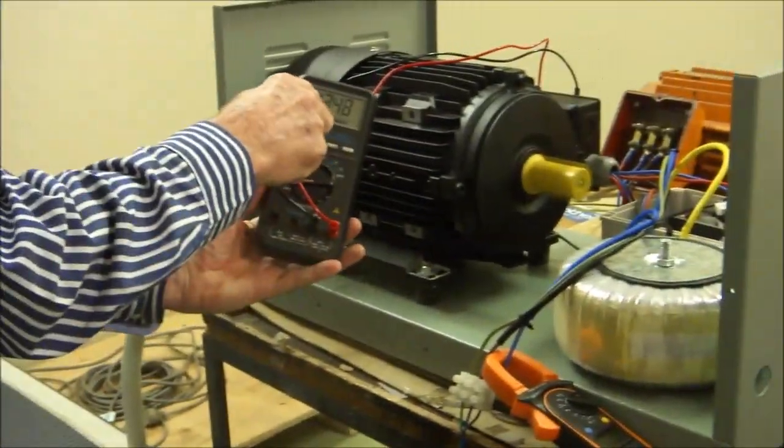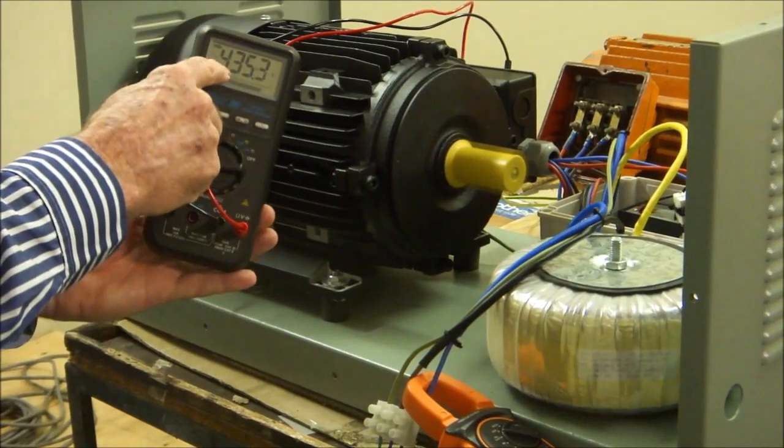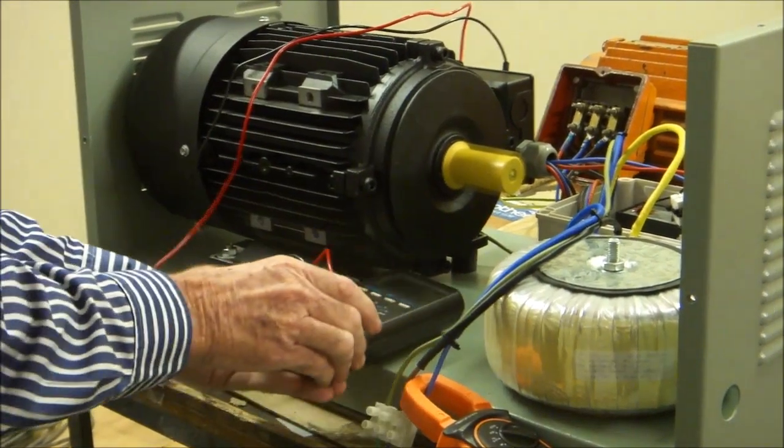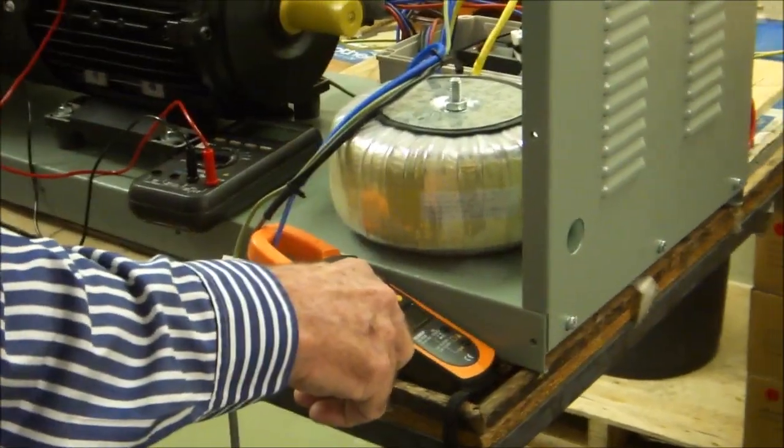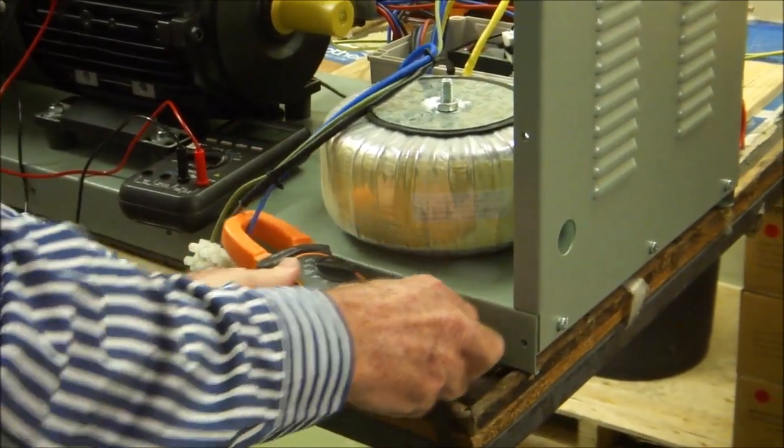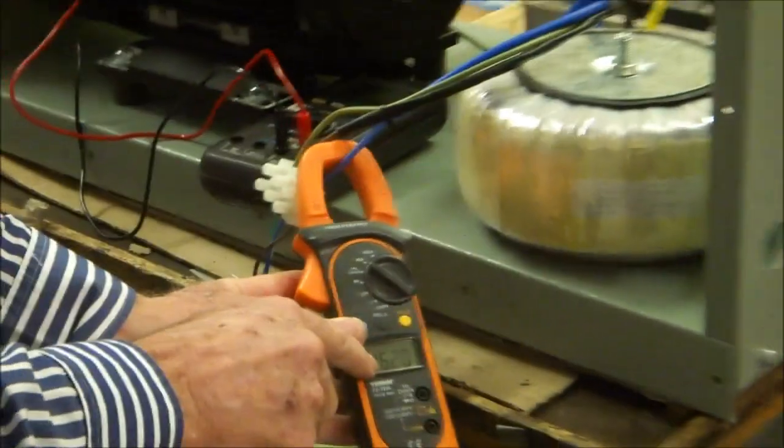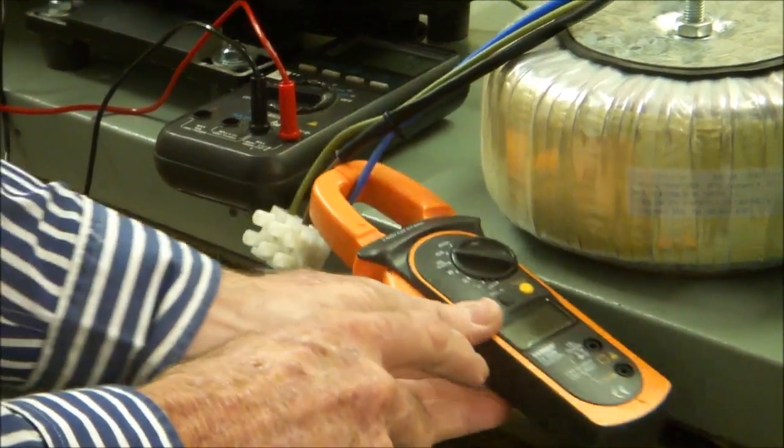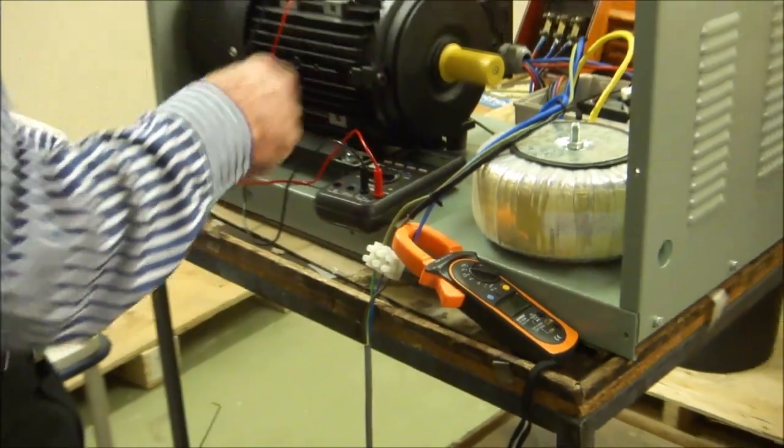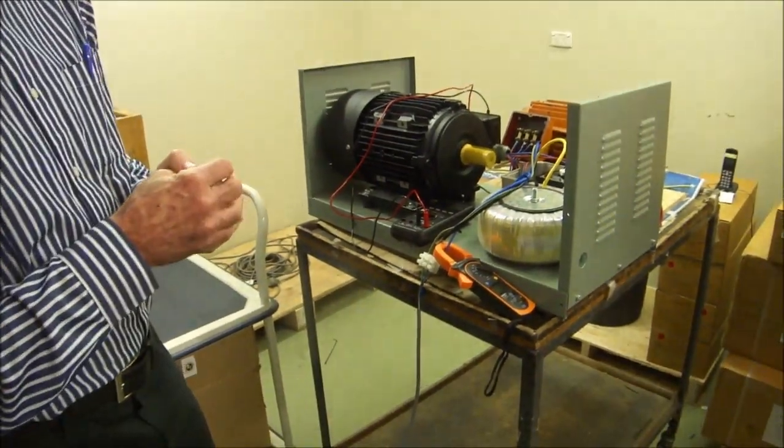Feeding the inverter, which is now reading 434 volts phase to phase. And the input current single-phase now is 16.2 amps per phase on the 240 volt side. And the load motor is now running.